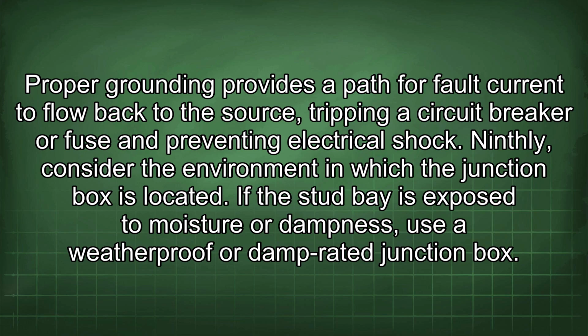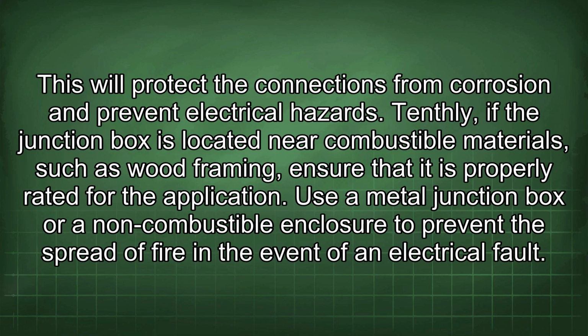Ninthly, consider the environment in which the junction box is located. If the stud bay is exposed to moisture or dampness, use a weatherproof or damp-rated junction box. This will protect the connections from corrosion and prevent electrical hazards. Tenthly, if the junction box is located near combustible materials such as wood framing, ensure that it is properly rated for the application. Use a metal junction box or a non-combustible enclosure to prevent the spread of fire in the event of an electrical fault.